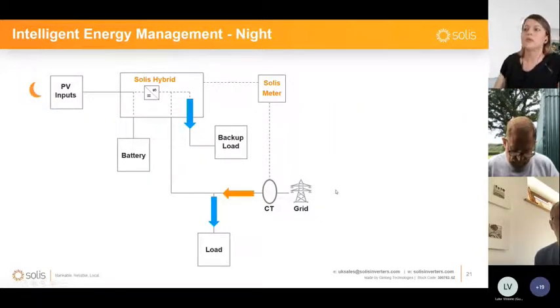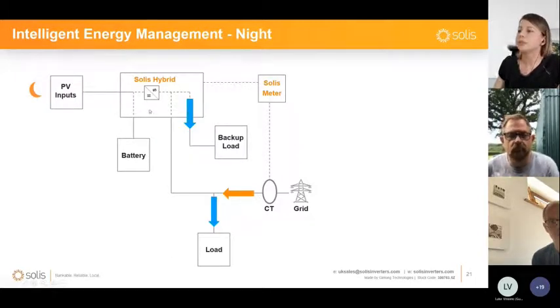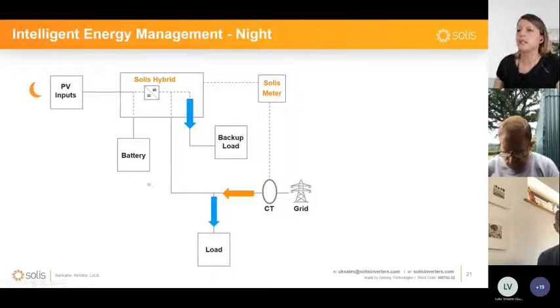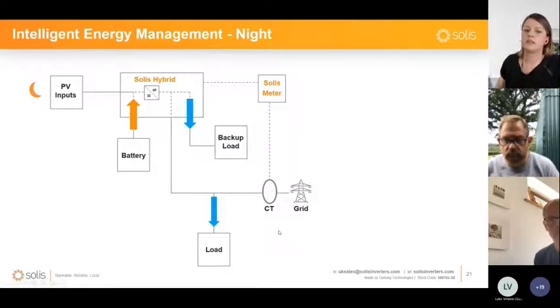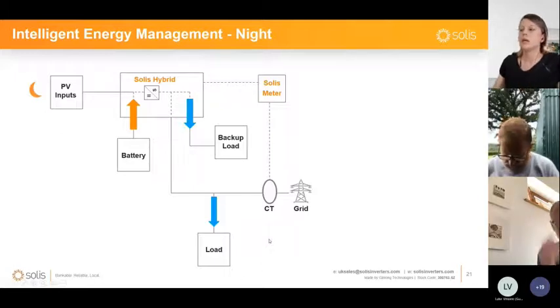Okay, so during the nighttime, normally the PV is out, no PV generation. So the load should start getting its power from the grid. What the Solis meter does is read that energy being consumed and send this information to the Solis hybrid inverter, and the inverter, by communicating with the battery management system, sees that it has energy available, and it will start discharging this battery in order to cover these loads and make this value that is being read by the CT clamp as close to zero as possible. So it will consume the energy that has been stored during the day, making it available now for the load.